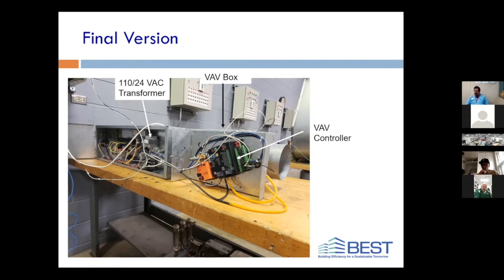This one was just, since it was the first time running it, we used lights to simulate activation of the 480 volt electric reheat coil on it. What we did is we operated the switch gear, but the contacts on the switch weren't connected to any 460 power. They just activated the light to say that the heat was on.